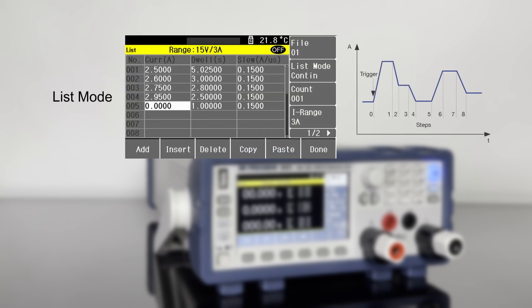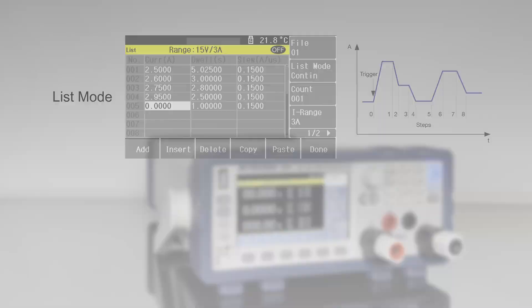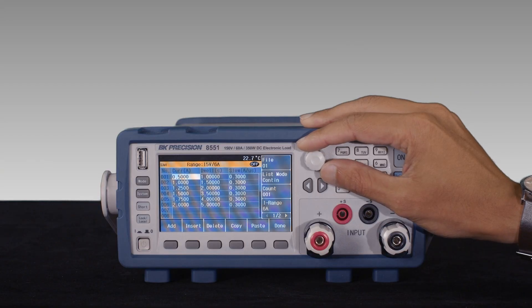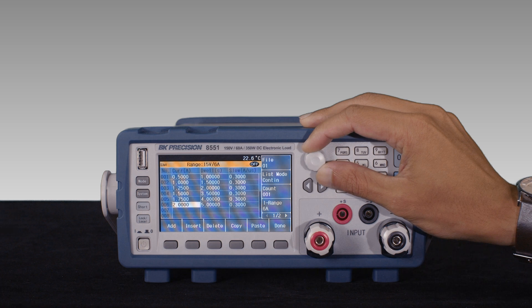List mode can be used to generate precise load sequences and is configurable from the front panel. Set load current, dwell time, and slew rate for up to 100 programmable steps.